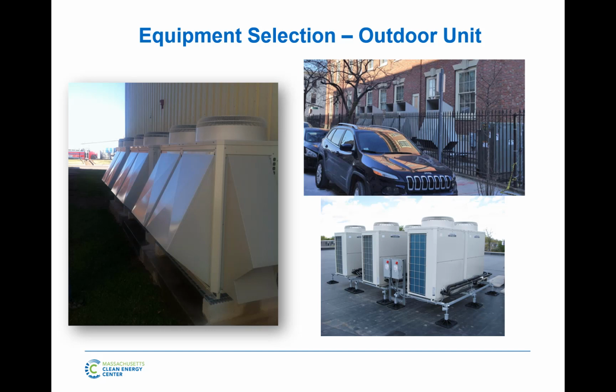The reason I like to point that out is when you're looking at the dimensions of this equipment, add an extra 12 to 18 inches, because you are going to need to lift it up off the ground. About a year ago, I completed a VRF system in a similar situation where we gave a presentation to an architect. They loved the system, they loved the flexibility, they saw the units and how easy they were to hide somewhere. And then up here is what we ended up installing. They were expecting one of these and they got this.